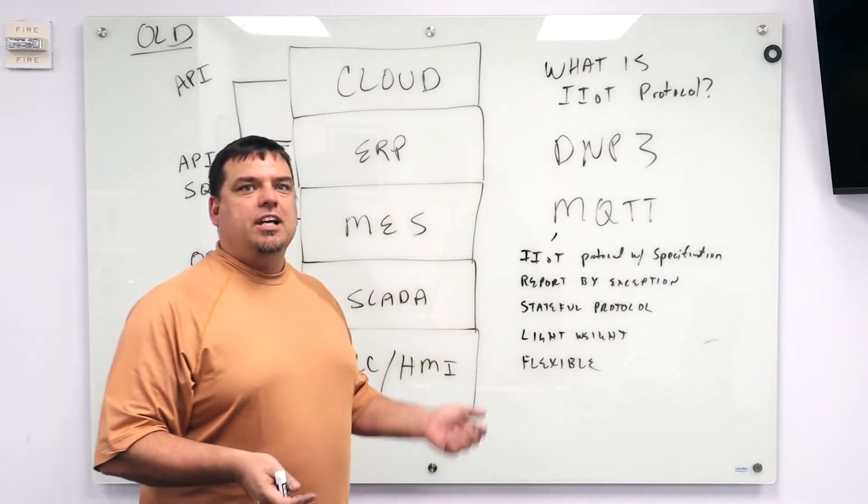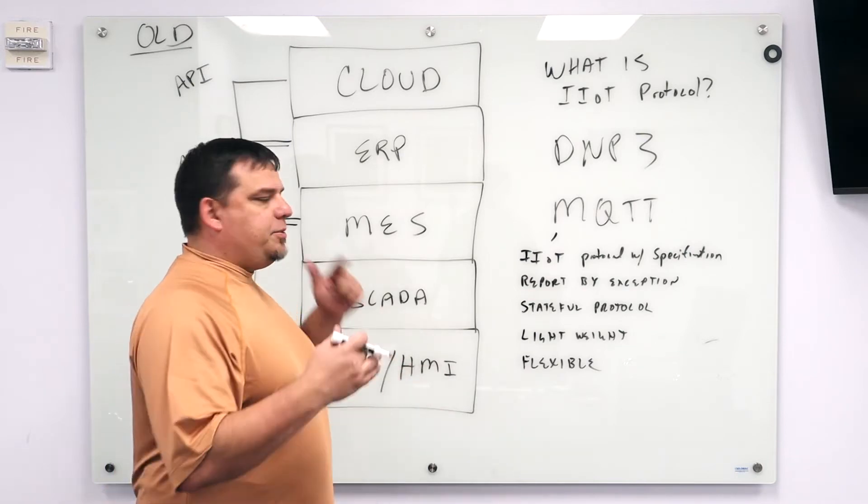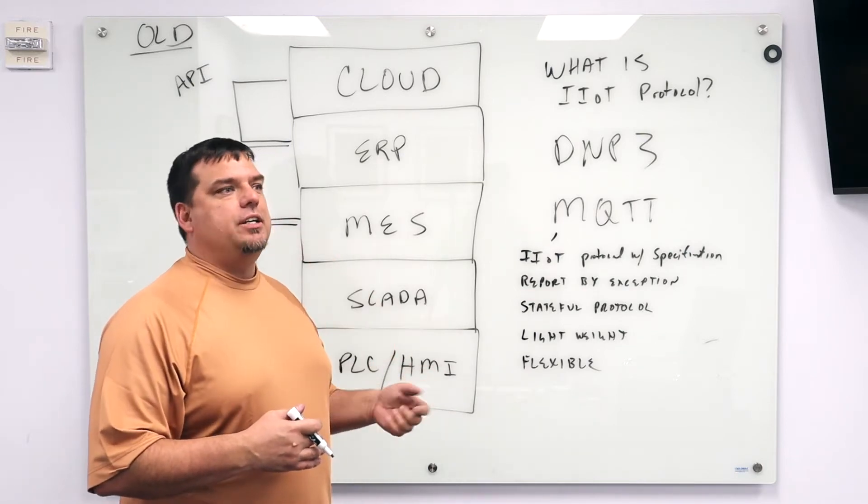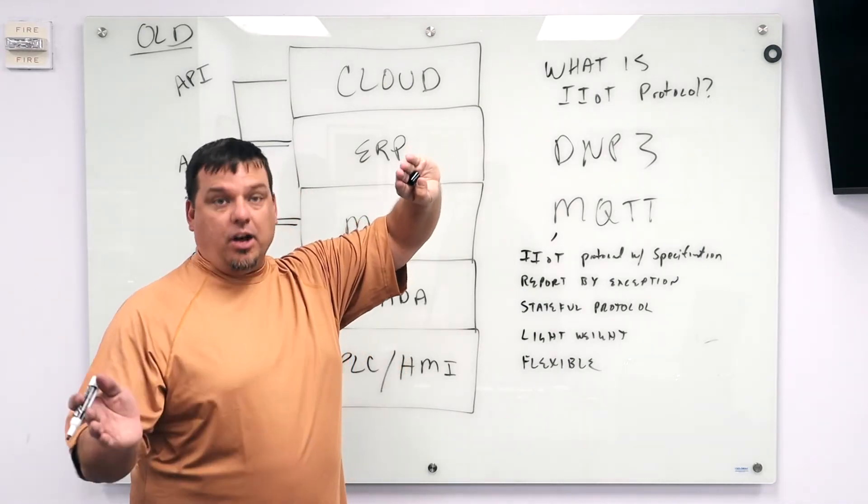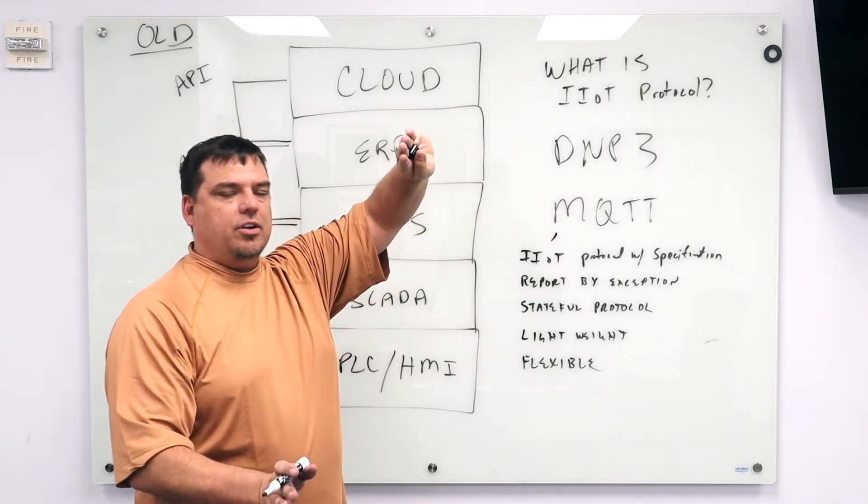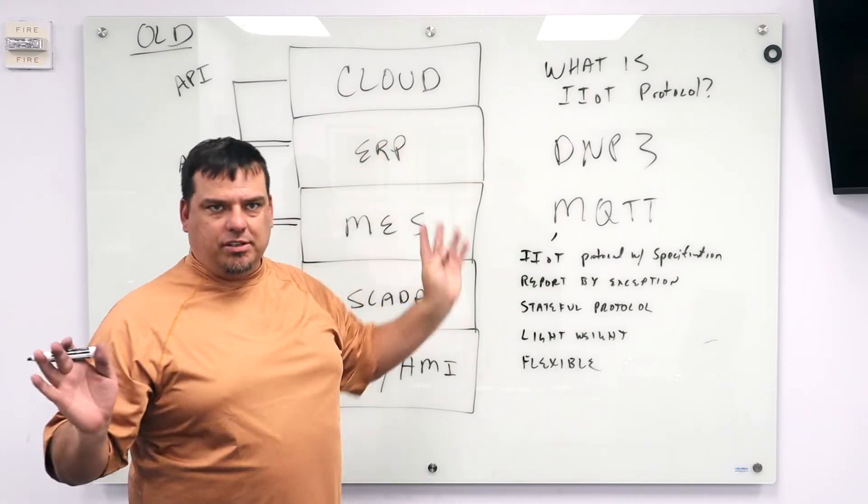You can go to the Eclipse Foundation. The Eclipse Foundation manages a specification called Sparkplug B. All the Sparkplug B specification tells you is how to connect something in the field to an MQTT server. We call them brokers. An MQTT server. And how do you format the data in the payload so that it can be organized at the server?